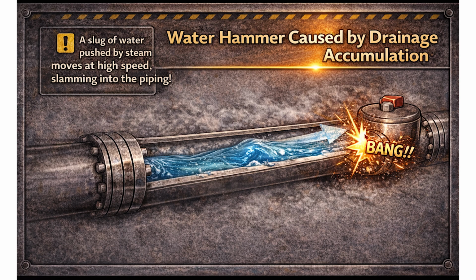Condensate inside the piping cannot be seen from the outside, but there is a clear sign that engineers often notice: water hammer. Not only during cold start, sometimes it occurs even during normal operation. You may occasionally hear a heavy sound, a bang, or a strong knocking sound. When this happens, condensate is often accumulating inside the piping.